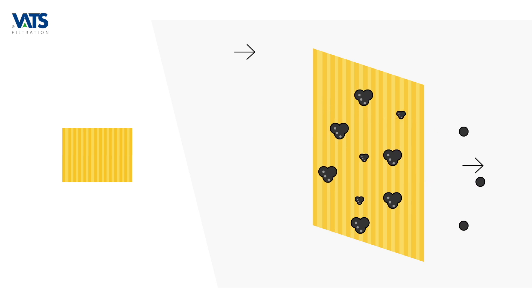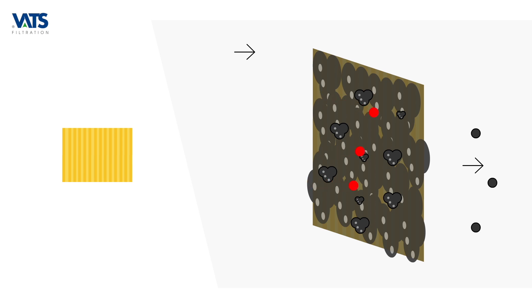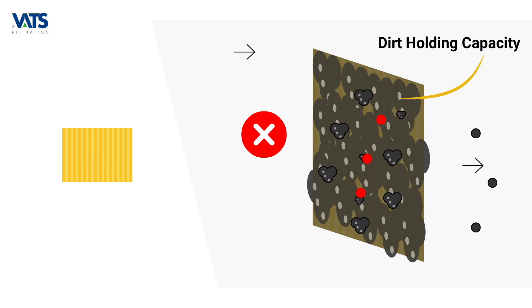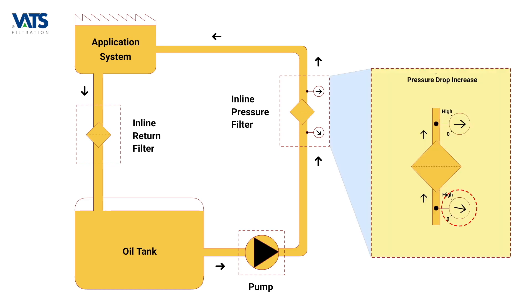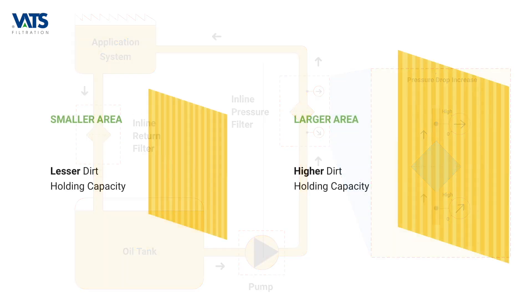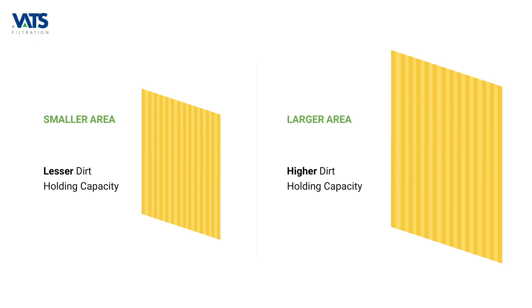As the holes on the mesh start getting used up by particles, lesser and lesser area is available for further flow, and eventually the sheet will get completely clogged, stopping the flow altogether and rendering it useless. The amount of dirt retained at this point is its maximum dirt holding capacity. However, in reality, the pressure drop across the filter starts increasing as the filter gets progressively clogged, and when the pressure drop is excessively high, the process needs to be stopped and the filter replaced.